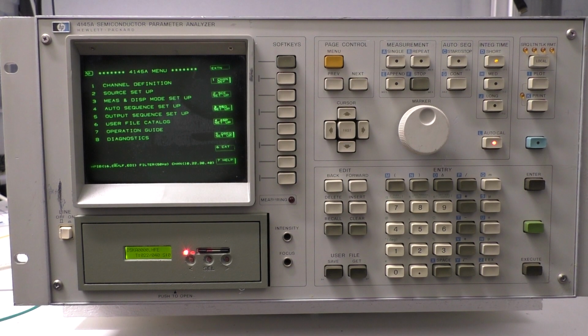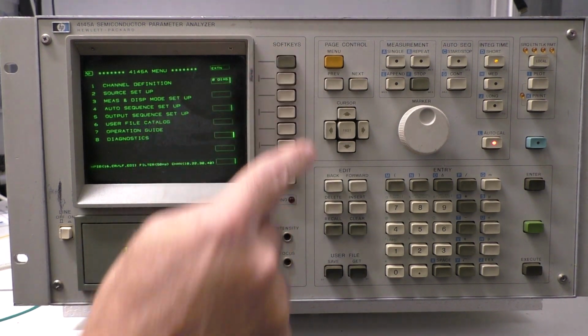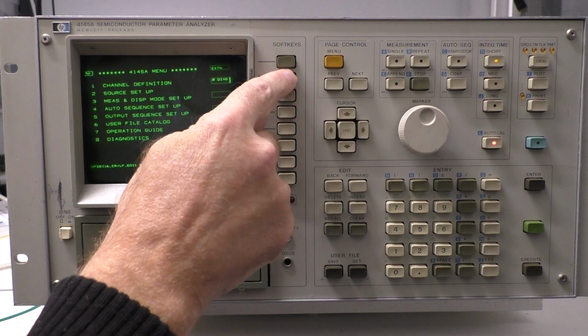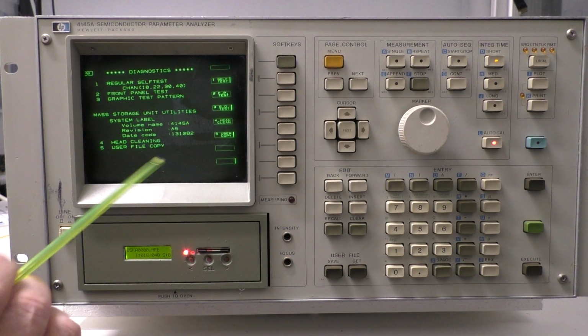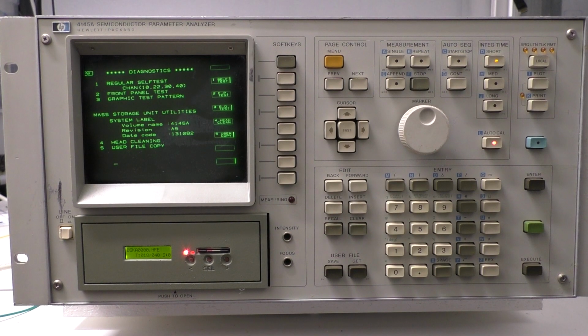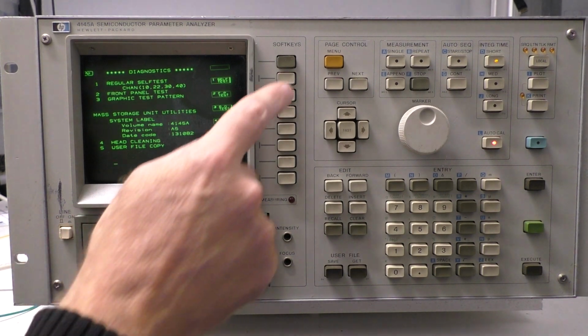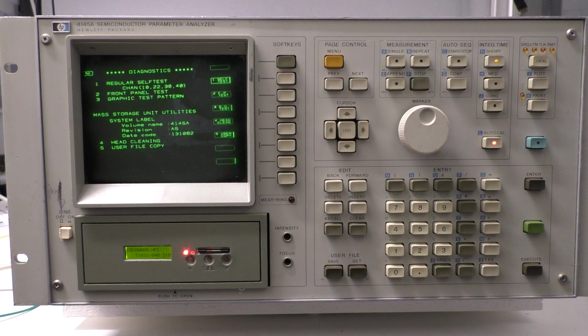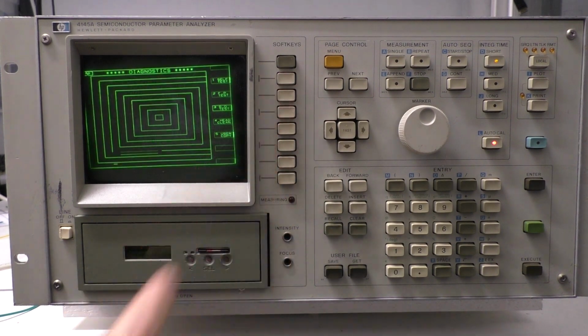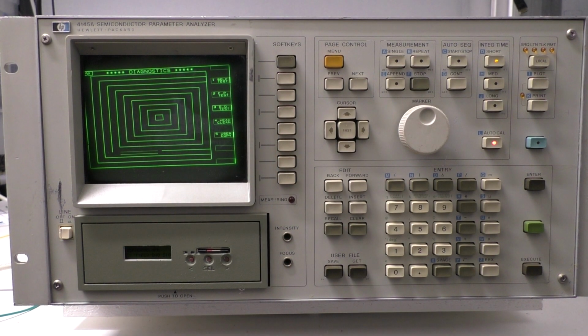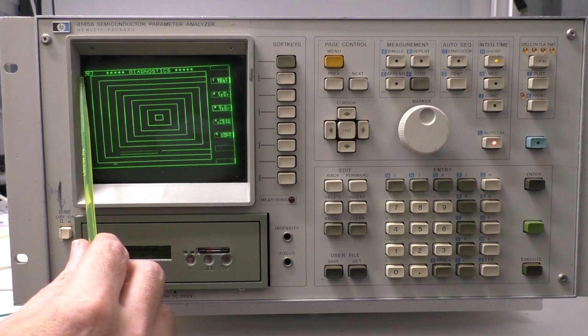Let's check out the software. Hit the extension Softkey. Then Diagnostics. We note the revision and date code as expected. Let's now perform a self-test. Looks good, no errors are reported on the screen. Perform a graphics test. This is as expected also, besides the skewed screen needing alignment.